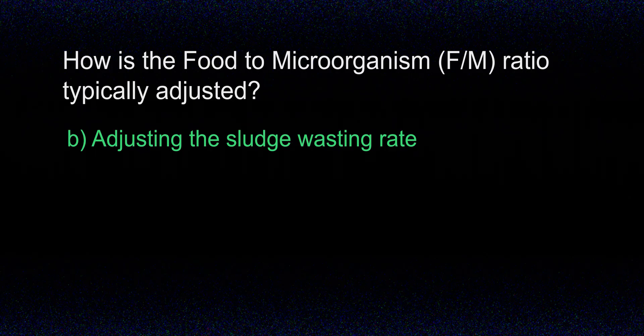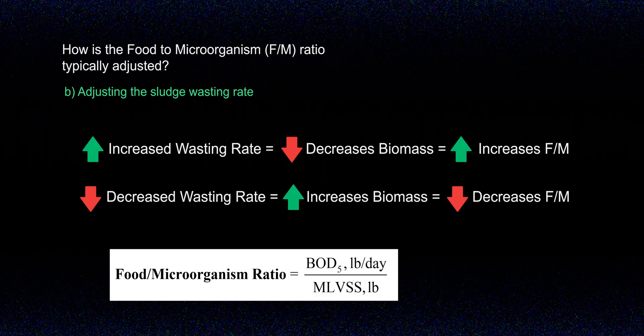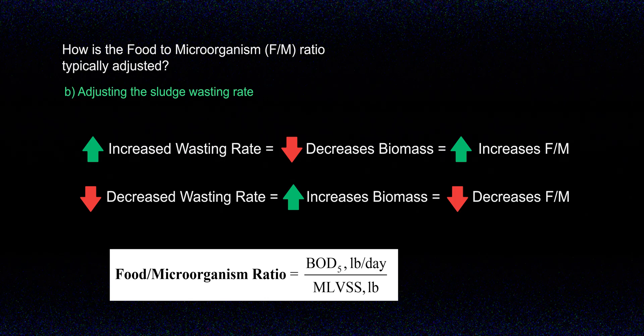The answer is B, adjusting the sludge wasting rate. The food to microorganism ratio, also called the food to mass ratio or F/M, represents the amount of BOD or CBOD available relative to the amount of microorganisms in the system. To control this ratio, operators must adjust the sludge wasting rate. When you increase the wasting rate, you remove excess microorganisms, reducing your biomass and increasing the food to mass ratio. On the flip side, decreasing the wasting rate retains and grows more biomass, which lowers the food to mass ratio. You need to track your mixed liquor volatile suspended solids (MLVSS) concentration to know how many microorganisms are in your system.